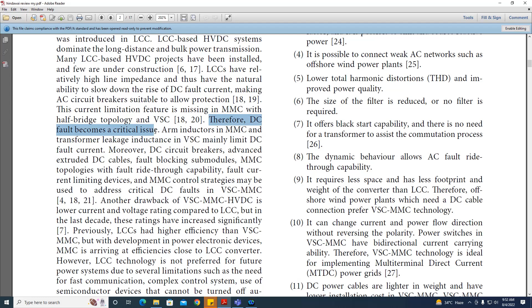In case of VSC and MMC, this feature is missing. Therefore, DC fault becomes a critical issue. DC fault is a very critical issue. Arm inductors in MMC and transformer leakage inductance in VSC mainly limit the DC fault current. Moreover, DC circuit breakers, advanced extruded DC cables, fault blocking submodules, MMC topologies with fault ride-through capability, fault current limiting devices, and MMC controls may be used to address critical DC faults in VSC and MMC. These are different ways to overcome the DC pole-to-pole short circuit fault condition.